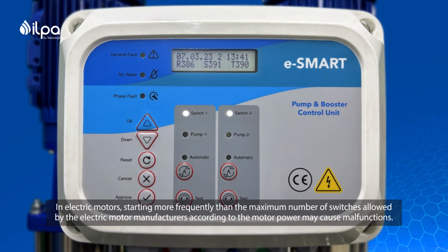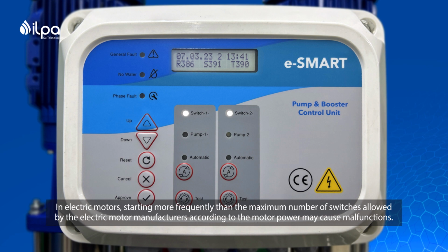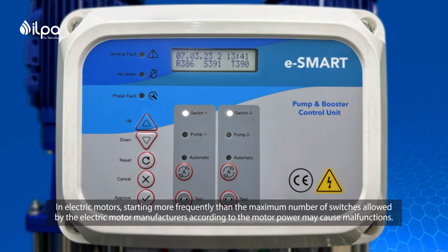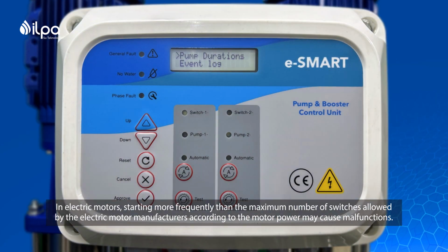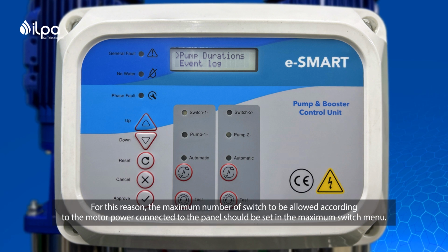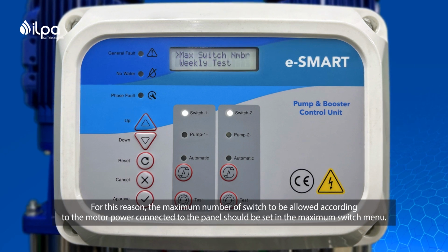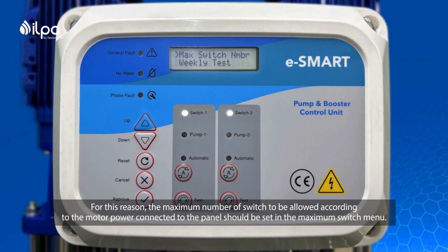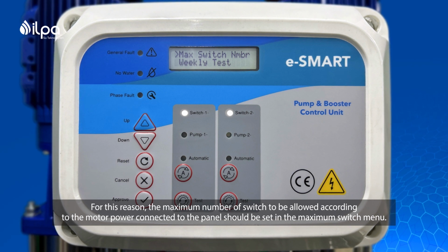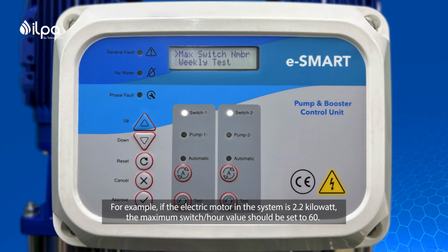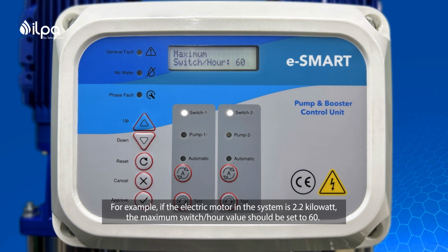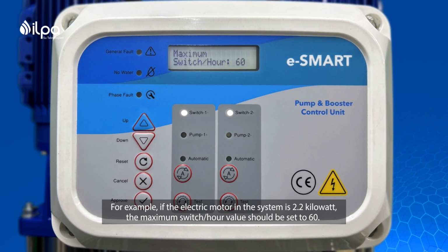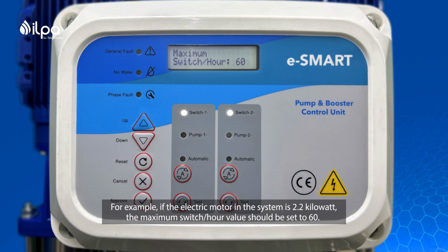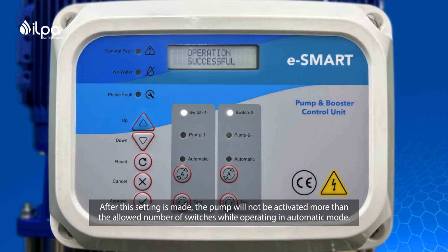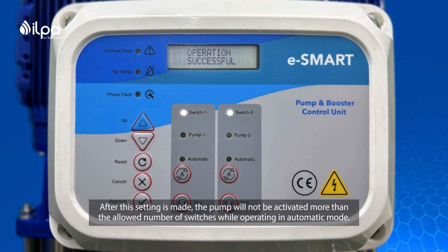In electric motors, starting more frequently than the maximum number of switches allowed by the electric motor manufacturers according to the motor power may cause malfunctions. For this reason, the maximum number of switches to be allowed according to the motor power connected to the panel should be set in the maximum switch menu. For example, if the electric motor in the system is 2.2 kilowatt, the maximum switch per hour value should be set to 60.